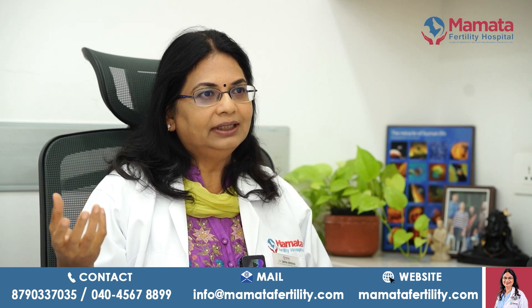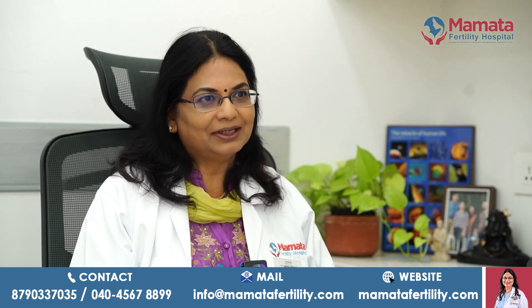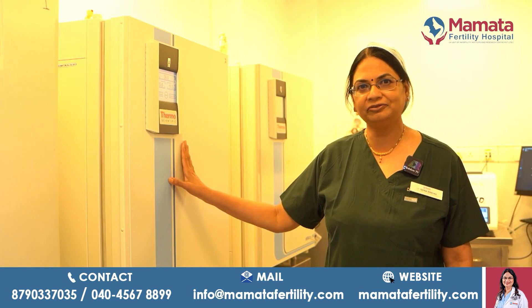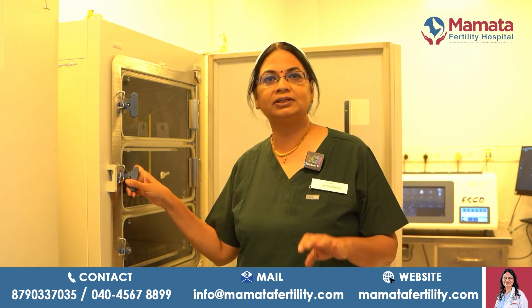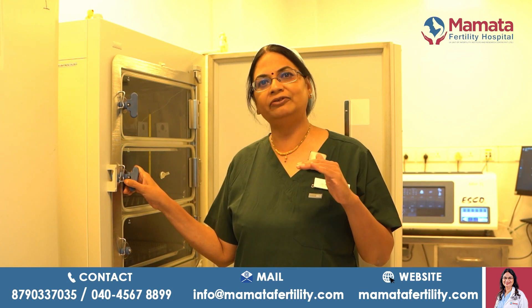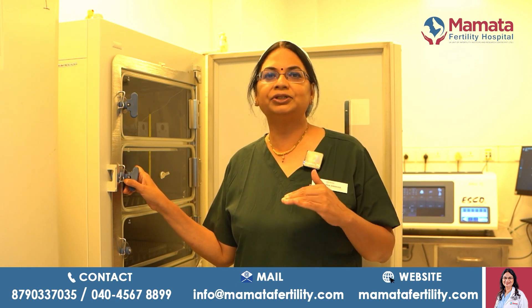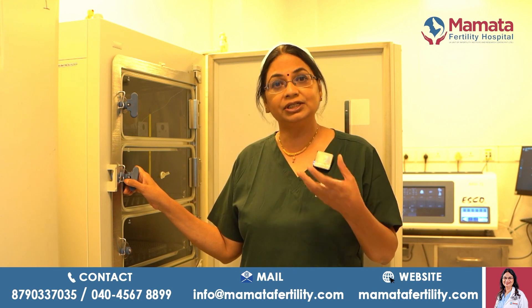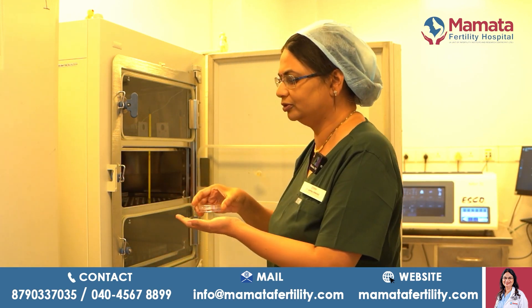The embryo is growing in an incubator. I'll take you into the laboratory and actually show you an embryo incubator, and we can also see how time-lapse is advantageous over regular incubators. This is a big box incubator used in IVF. Inside is a very controlled environment where the temperature is kept at 37 degrees centigrade, CO2 is kept at a level where the pH is maintained at 7.2 in the culture medium, and oxygen saturation is kept at 5 percent. This controlled environment ensures the embryo grows continuously, mimicking what happens in the tube of the woman.